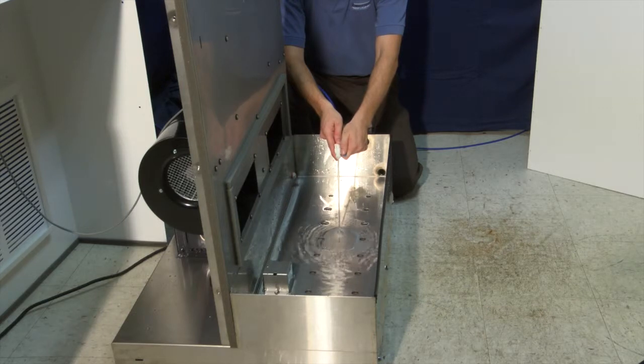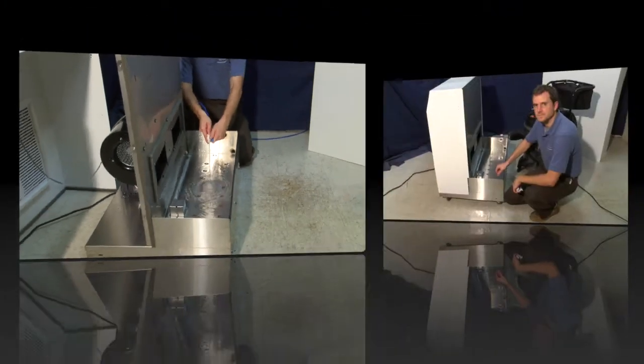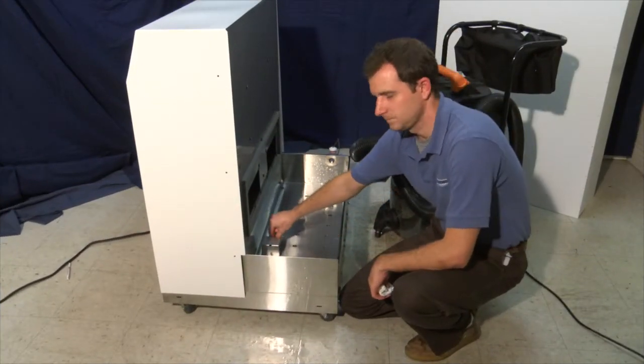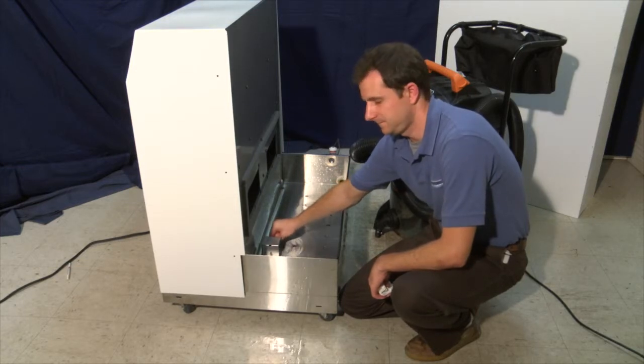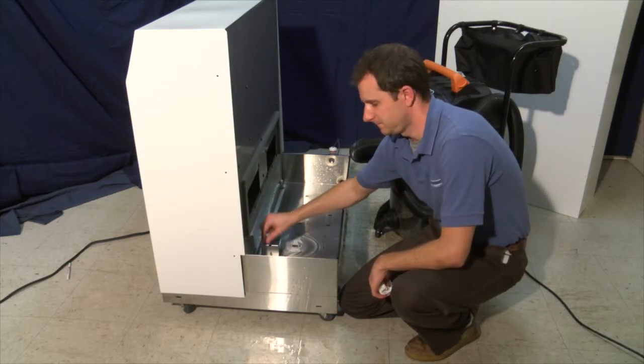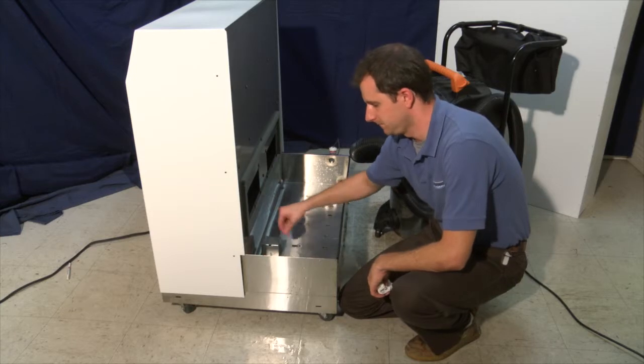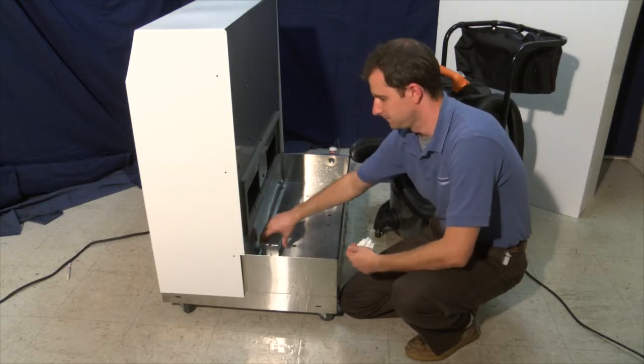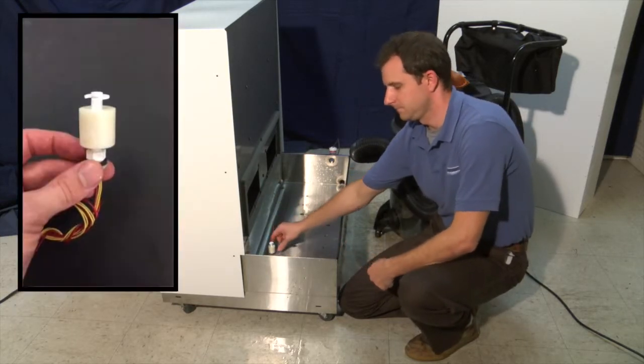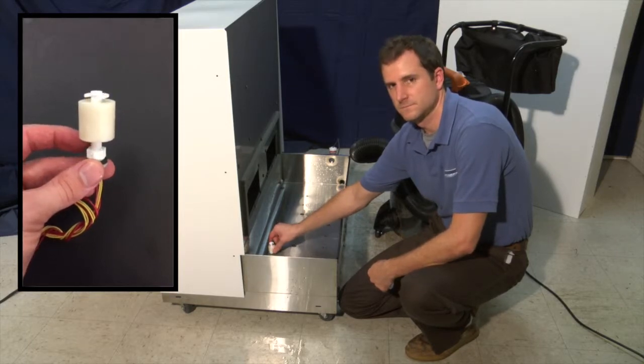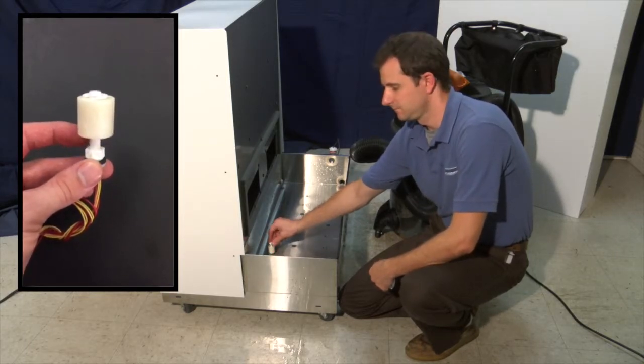If you clean it regularly, it will be fast and easy to manage. If you wait until it is a murky, dirty mess, it will be that much harder to fully clean, and damage may already be done. It is also necessary to ensure the float switch inside the water pan can move up and down properly. This float is a dual stage float that both communicates with the solenoid in order to keep the Mist-Free filled with the prime amount of water, and will also shut down the humidifier in the event of low water.